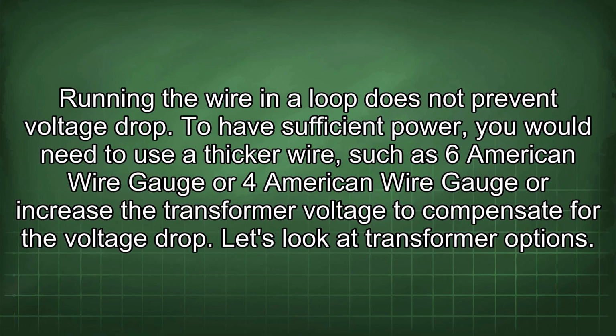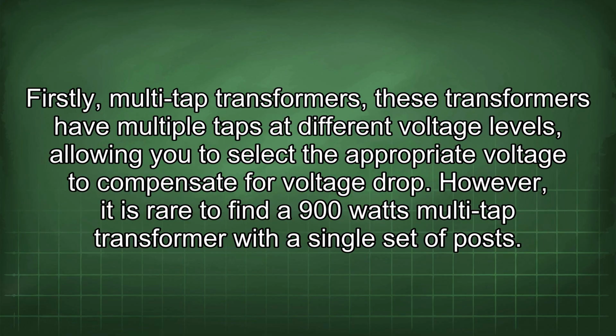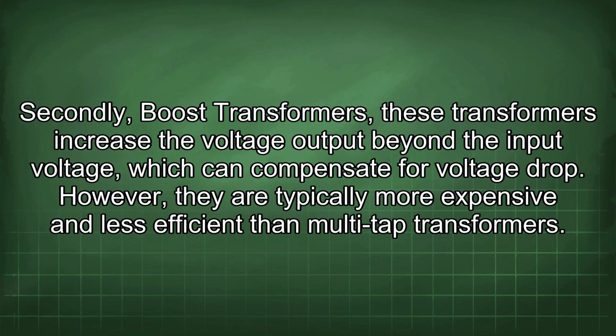Let's look at transformer options. Firstly, multi-tap transformers. These transformers have multiple taps at different voltage levels, allowing you to select the appropriate voltage to compensate for voltage drop. However, it is rare to find a 900 watt multi-tap transformer with a single set of posts. Secondly, boost transformers. These transformers increase the voltage output beyond the input voltage, which can compensate for voltage drop. However, they are typically more expensive and less efficient than multi-tap transformers.